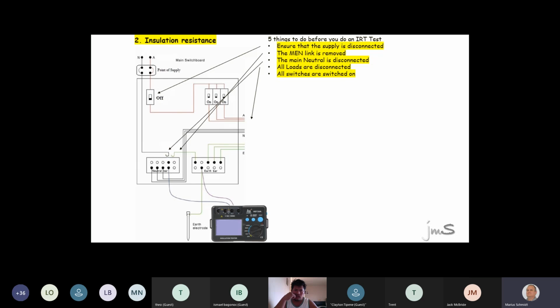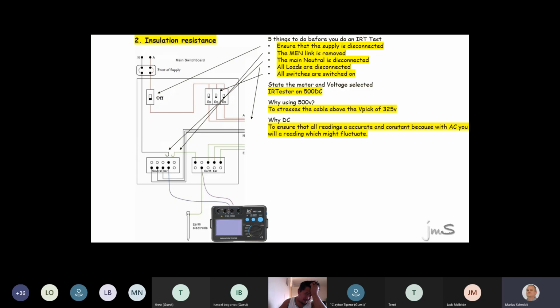So there we go, and we're now going to do a wonderful test. We're going to use the insulation resistance tester at 500 volt DC. Why 500 volt DC? We must ensure that our test voltage is greater than 325 volt peak. If you don't know how to get the volt peak, take your calculators and say 230 divided by 0.707. Have you guys ever heard about 0.707? That gives you peak voltage. Right, to carry on, why DC? I told you guys earlier, to get an accurate reading.